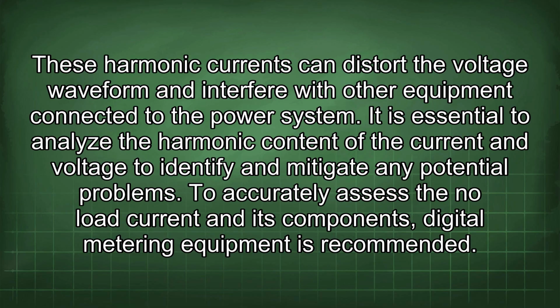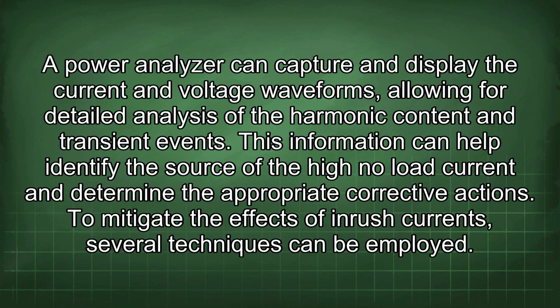To accurately assess the no-load current and its components, digital metering equipment is recommended. A power analyzer can capture and display the current and voltage waveforms, allowing for detailed analysis of the harmonic content and transient events. This information can help identify the source of the high no-load current and determine the appropriate corrective actions. To mitigate the effects of inrush currents, several techniques can be employed.